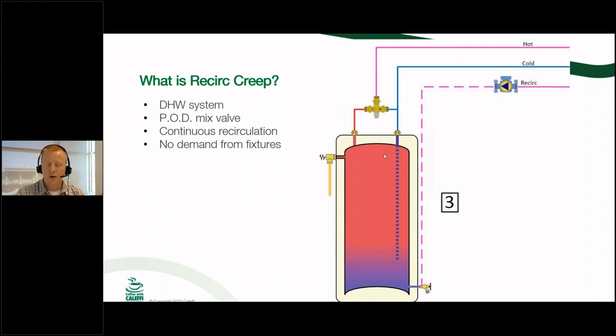And I've got some other scenarios and other piping diagrams going forward here that will make more sense of why you would actually need to use that recirc tapping or that bottom tapping there too. So from there, again, we're going to go back to that first drawing, because again, most common and everything like that here. And we're going to talk about, again, the fact that the recirc's coming back. It's going to go down the cold inlet. It's going to either go to the cold inlet of the mixing valve or through into the tank and back around again. Okay.